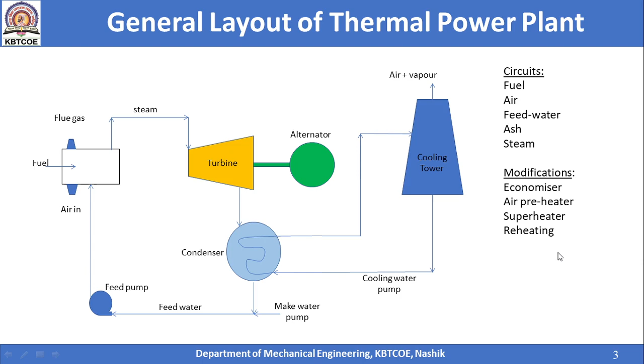We can also call it as a simple layout of a thermal power plant because the modern thermal power plant is quite complicated, and that we will see in the next slide. It should be noted that there are several circuits in a thermal power plant, and understanding these circuits will make it easier to understand the thermal power plant. These circuits are fuel circuit, air circuit, feed water circuit, ash circuit and steam circuit. In order to increase the efficiency of a thermal power plant, several modifications are there and several additional devices are incorporated in it called as economizer, air preheater, superheater, and several techniques such as reheating and regeneration are used to increase the efficiency.